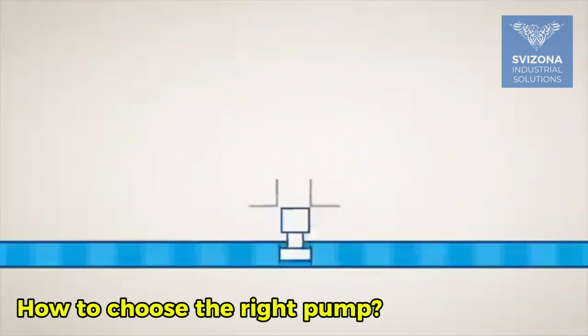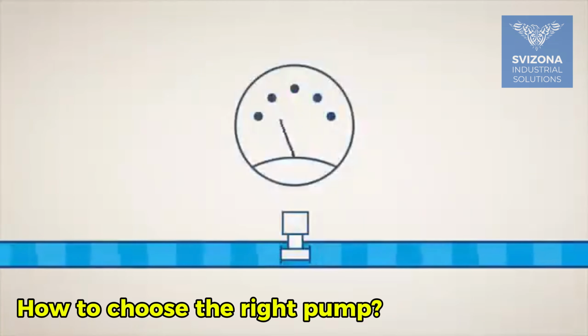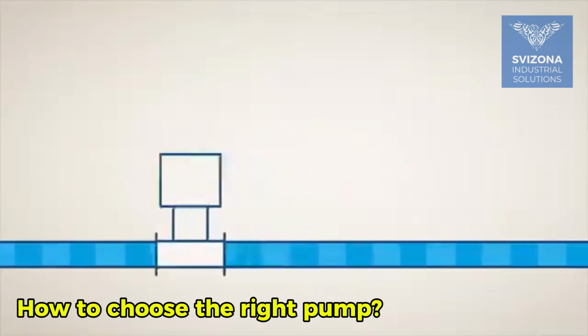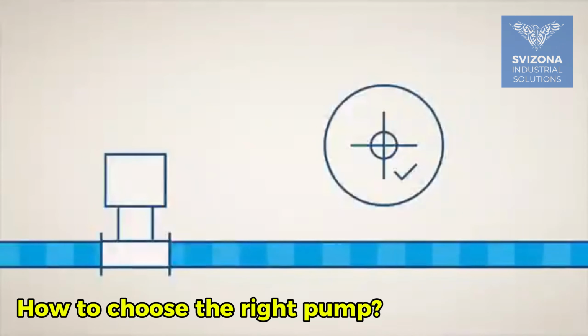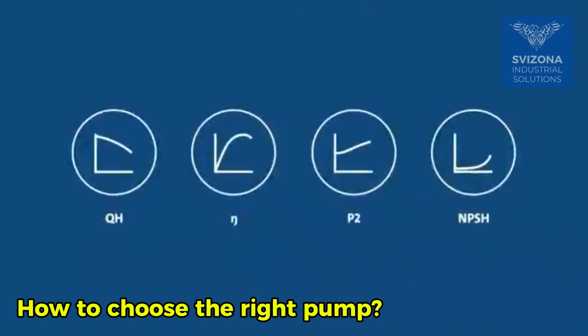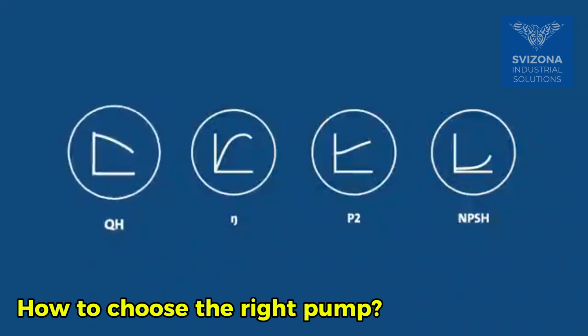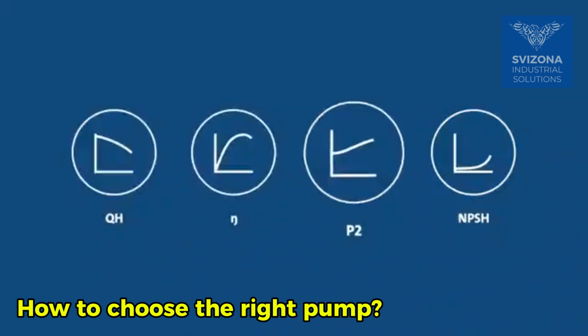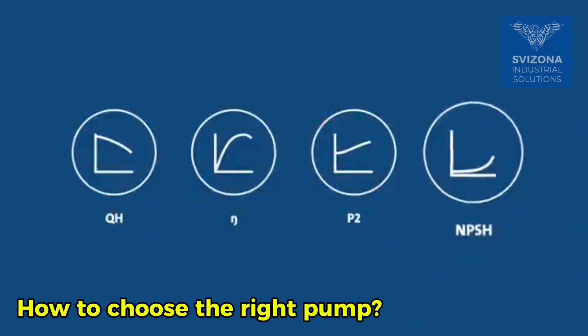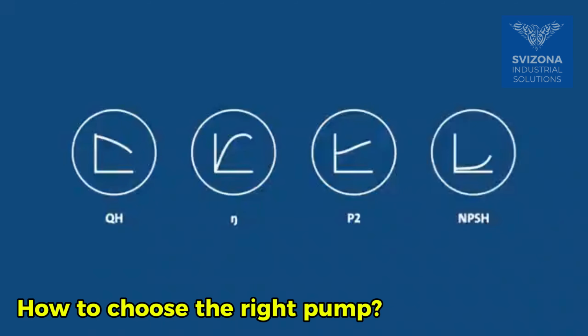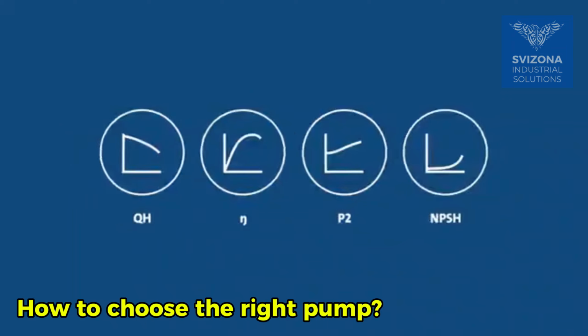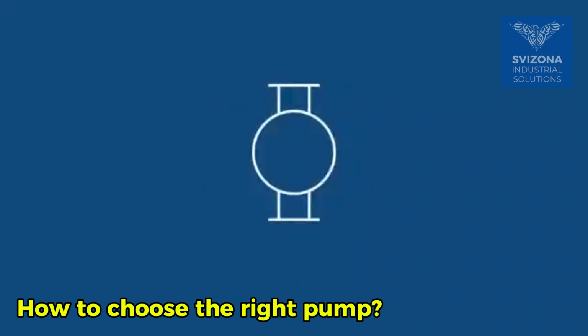Oversizing and undersizing a pump can have performance consequences, so you ought to stay as close to the duty point as possible. Now, let's take a look at a couple of common pump curves, namely the QH curve, the ETA curve, the P2 curve, and the NPSH curve. Together, these four curves provide a good overview of the performance of a specific pump, so we recommend including them in the same datasheet.